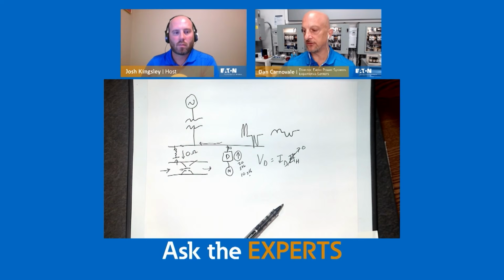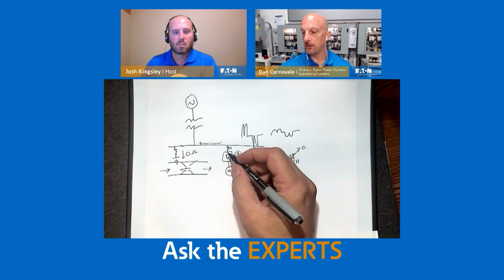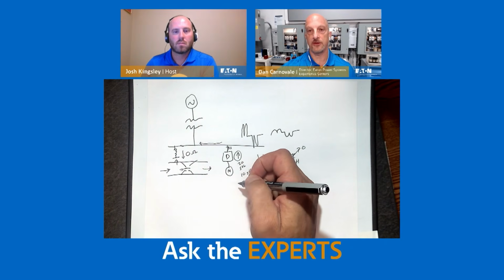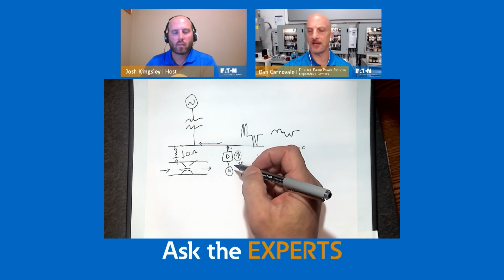The other thing is to select perhaps the right drive. We talked about 18 pulse clean power type drives. Our medium voltage drives, perhaps 24 pulse to keep that limit down to a reasonable level. And then you go all the way up through broadband filters in front of the drives and active front ends and so forth. So there's a lot of different solutions.